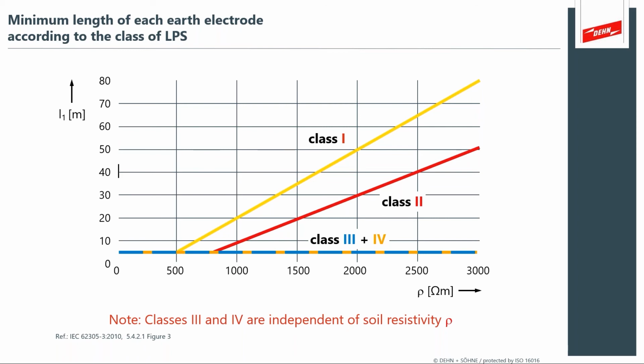So the earth electrode has to be in lockstep with your class of protection. And with a less severe class of protection, where you have perhaps less risk of fire and loss of life, you have a more relaxed electrode system. And that enables you to use a chart like this to understand your soil resistivity and then apply an earth electrode system suitable for that class of lightning protection and risk control. So that's what's really nice about this slide. It shows you the earth electrode helps control that lightning damage.